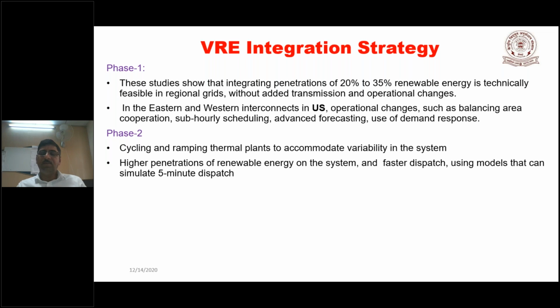They will generate 180 gigawatt, but the load may be 190 gigawatt. Since it's very difficult to forecast the load, if there's hardly a 5% error in the load, that will make it roughly 190 gigawatt. So the 10 gigawatt surplus, who will give it? If nobody gives it, it will result in a fall in the frequency, and that is not allowed. So somebody has to compensate for that increase in the load. Since these conventional powerhouses are equipped with governors, there will be automatic governor action, and accordingly they will increase their power generation by a certain rate. That's the advantage I have with the synchronous machine.